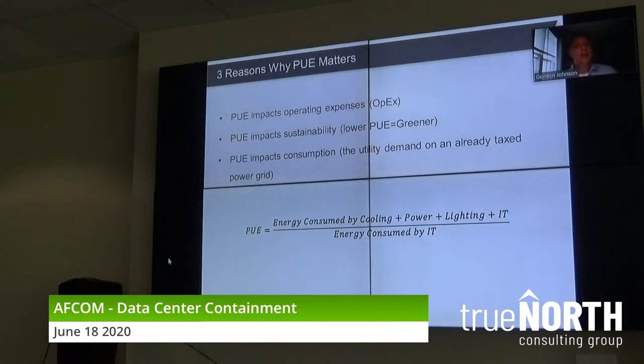When we look at existing legacy data centers, it's not uncommon for people to say my PUE is 2.0. And just so you can understand what that means, if you have a PUE of 2.0, for every kW of heat being generated by your IT equipment, it takes another kW to get that heat back out of the room. So that would be the definition of a PUE equals 2. And a PUE of 2 is average, but it's not energy efficient.